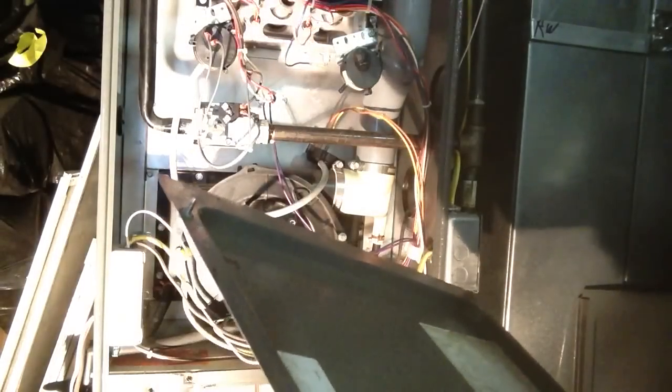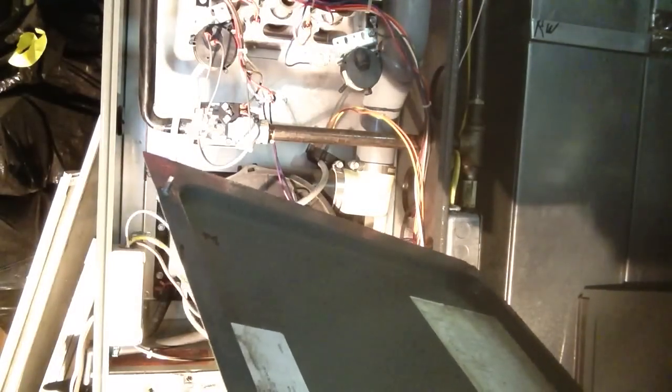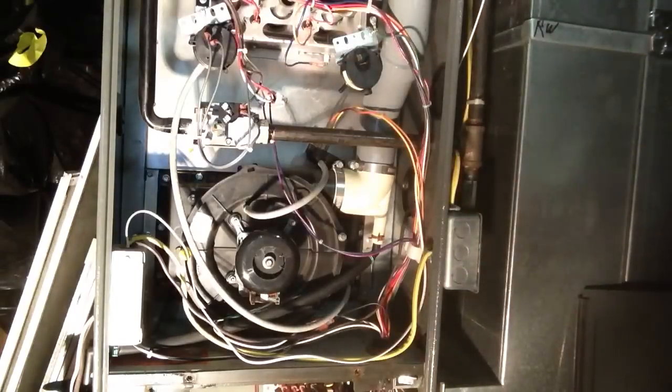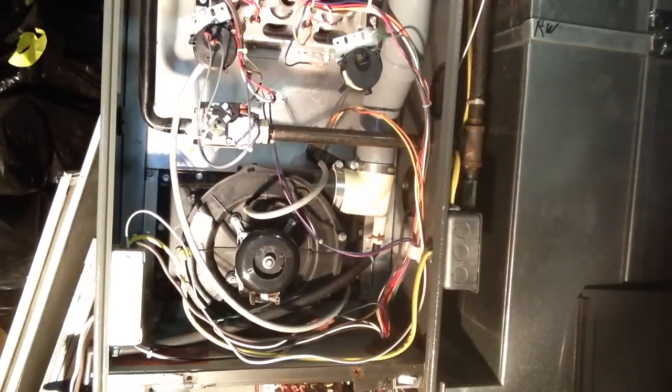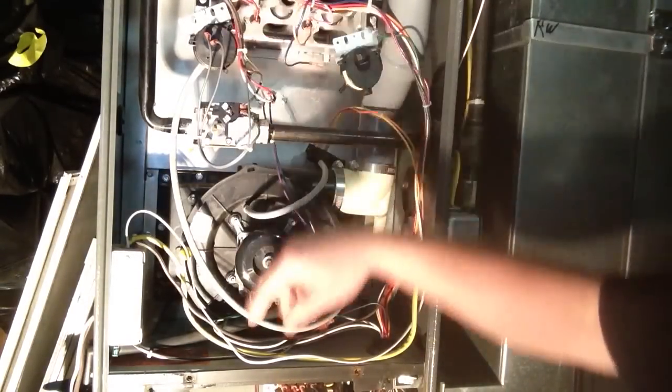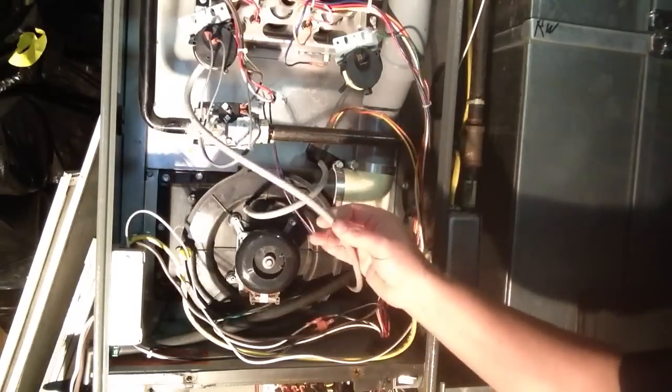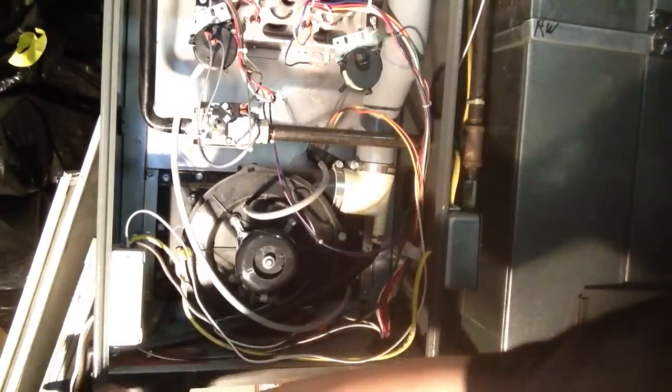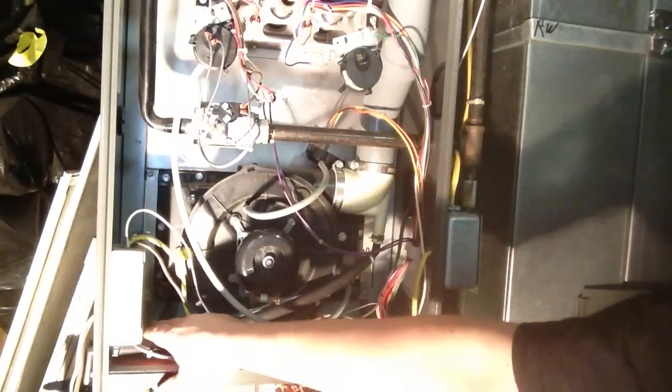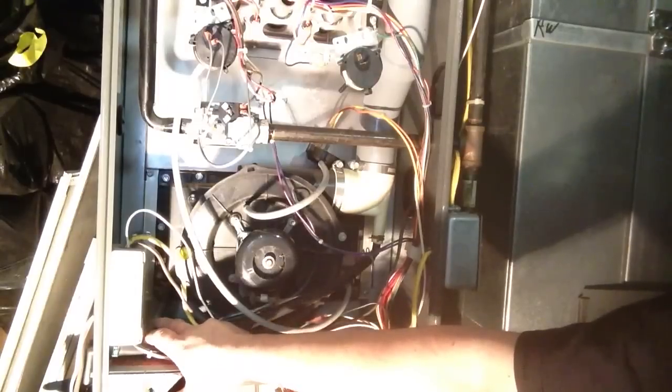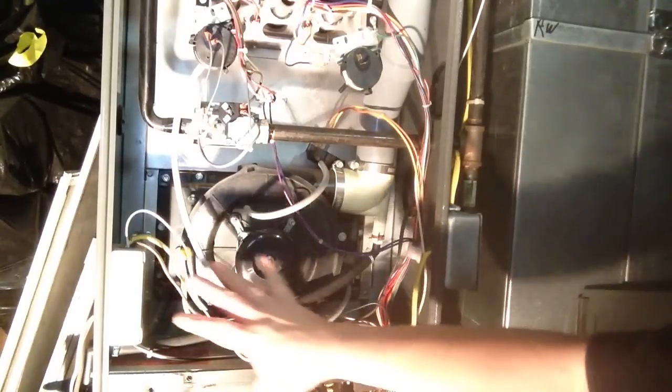Number three is pressure switch stuck open. Same thing. If they're stuck open or closed, look for water lines. Make sure your drain is open. Make sure your heat exchanger isn't full of water.